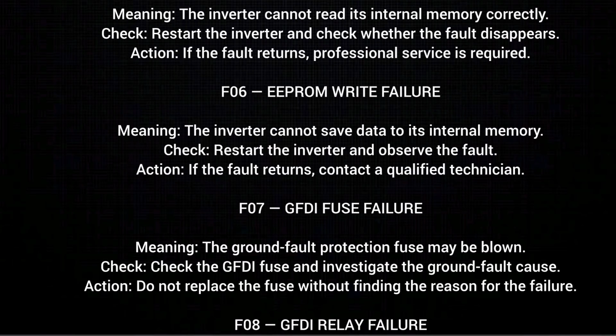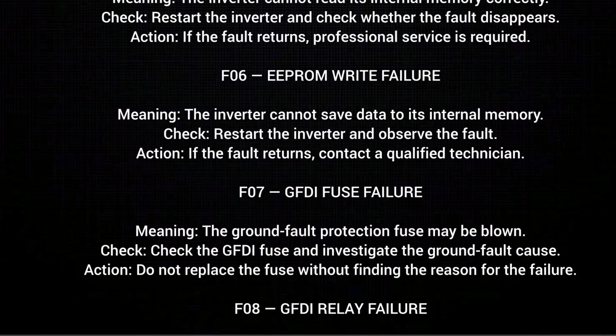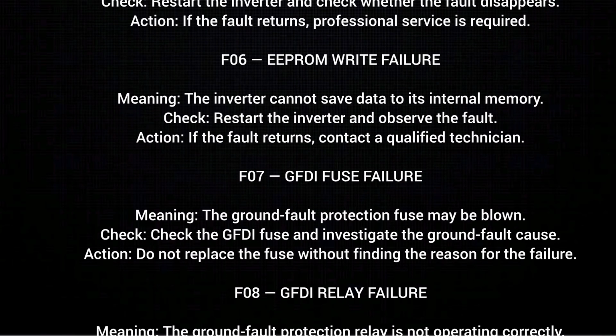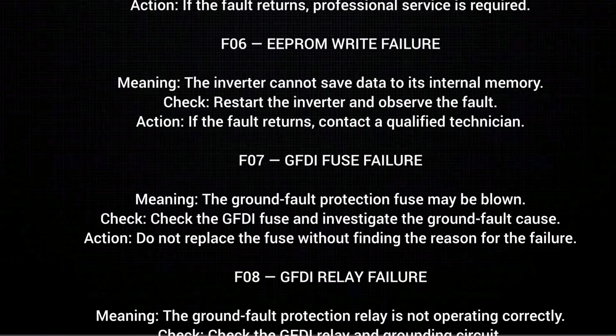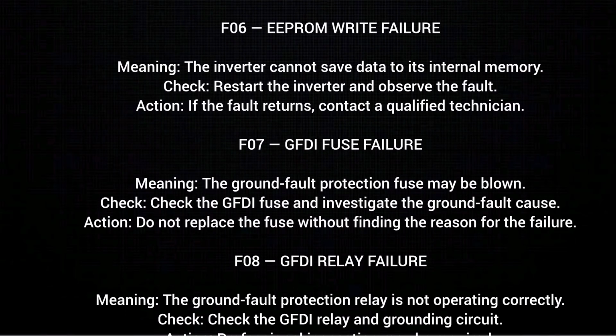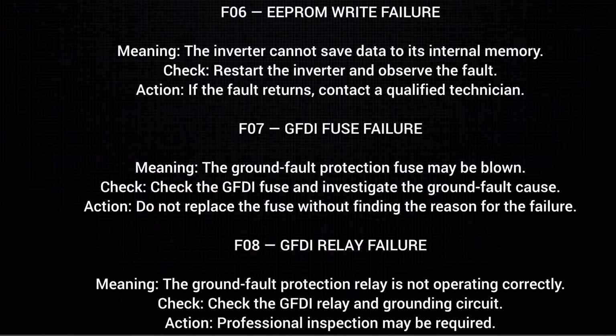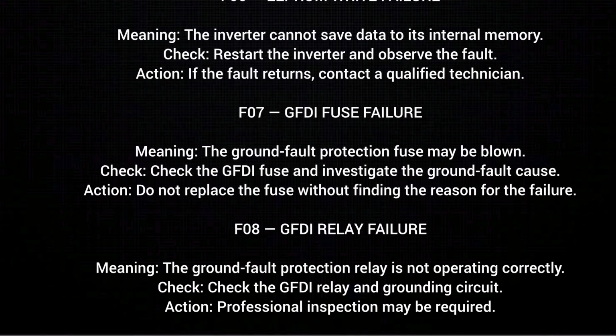F06 EEPROM write failure, meaning the inverter cannot save data to its internal memory. Check. Restart the inverter and observe the fault. Action. If the fault returns, contact a qualified technician.